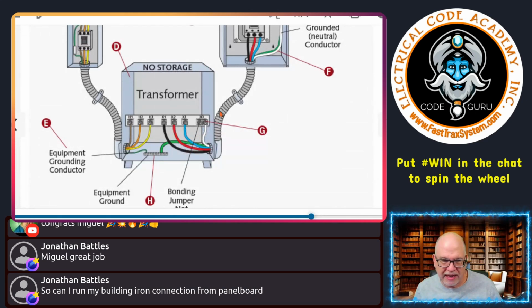We're not relying on this here, because typically this is FMC and it's sized, and it's bonded because it's a KO and it's punched out. There's no need for a lay-in lug here. As long as you're using a listed fitting, listed wiring method, we're not using it as an equipment grounding conductor. We're just meeting the bonding elements here. And you're typically not.